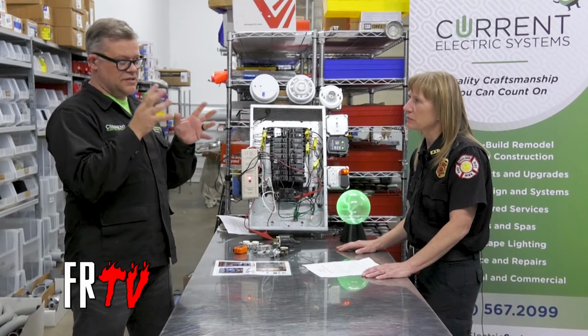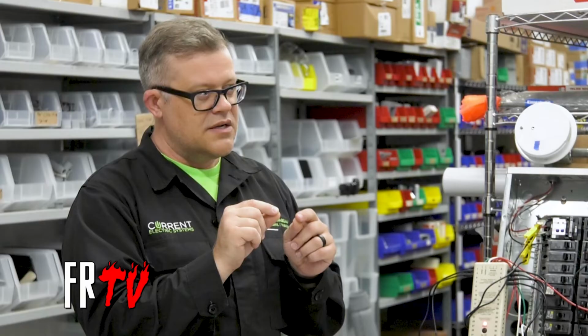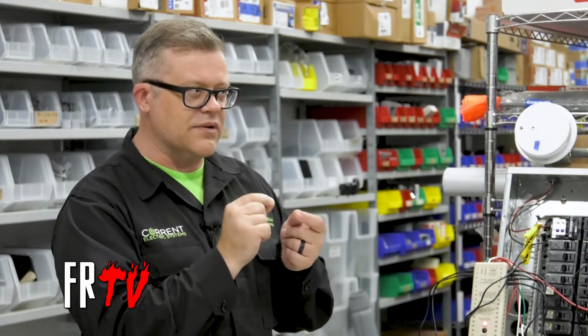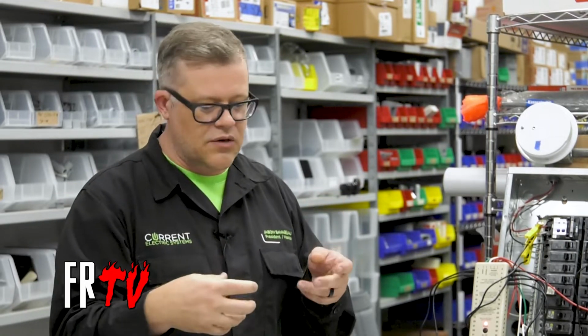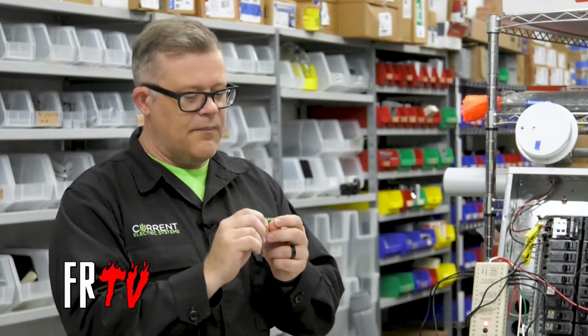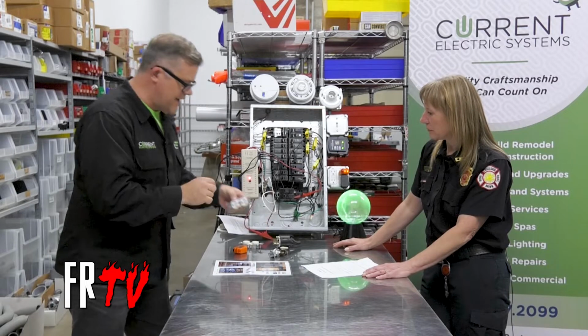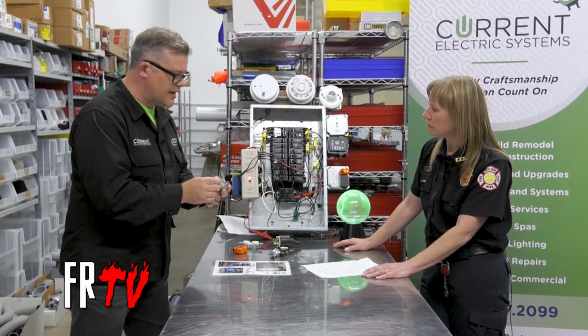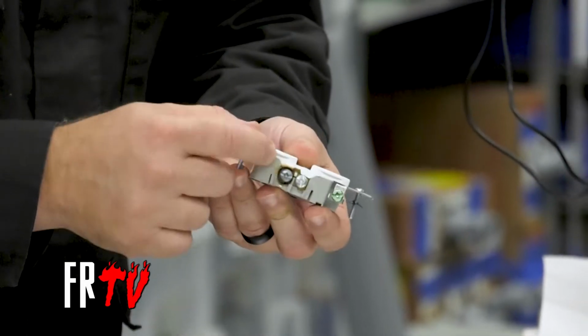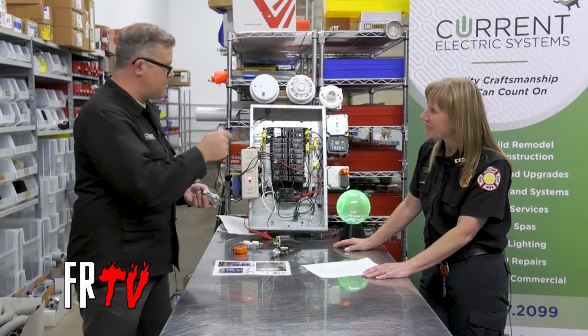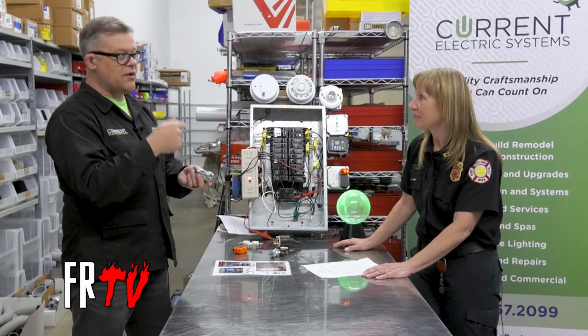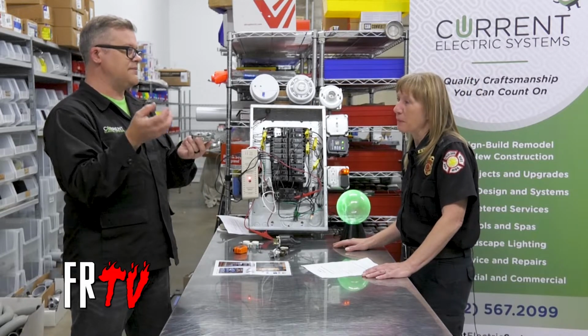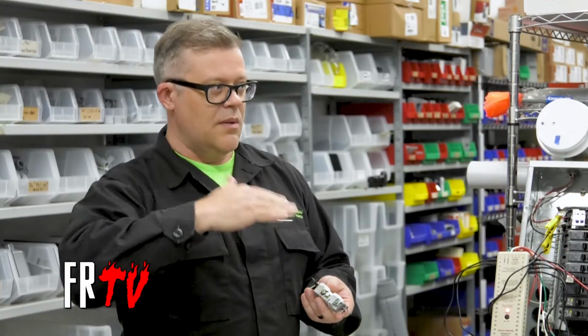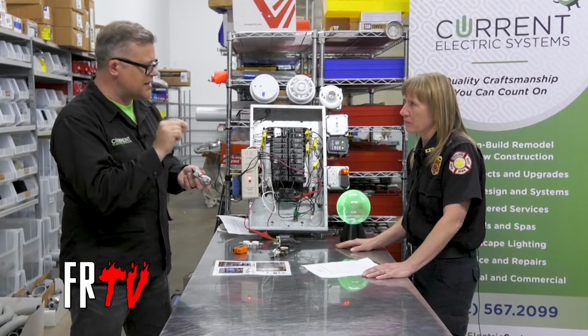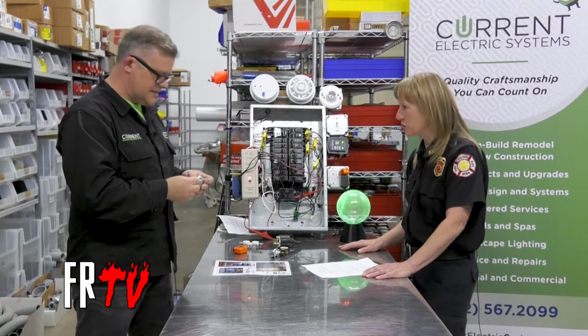The AFCI is monitoring the circuit for arcing conditions. Let's say you have a loose wire on a receptacle, and you're plugged into your space heater, your big TV, or stereo - doesn't matter. The connections start loosening up, and I have an example of what can occur: burn marks where the wire was connected. This will not trip a normal breaker, but it will trip an AFCI. It's a technology that attempts to mitigate those sparking fire starters, preventing a fire. Exactly, it's fire prevention.